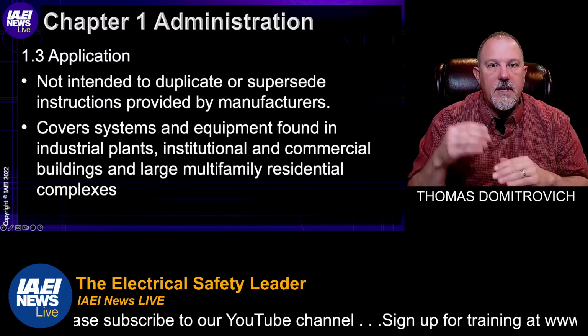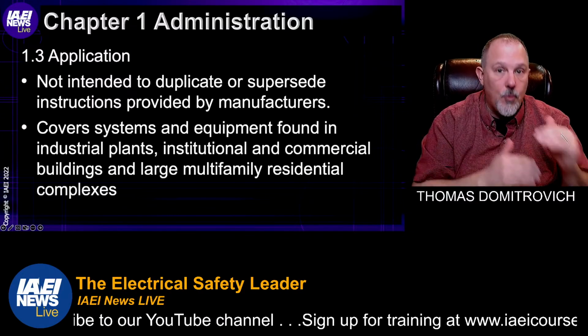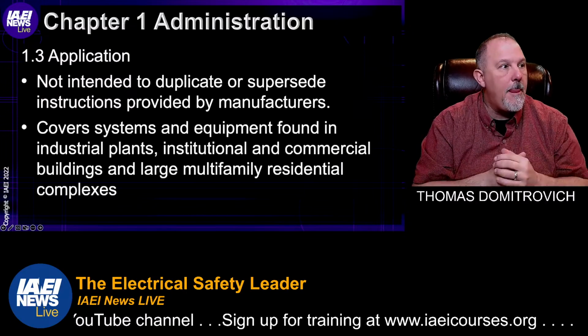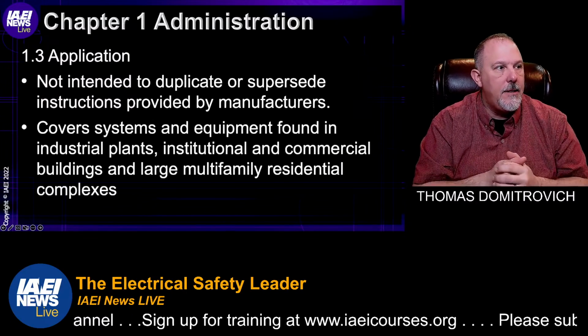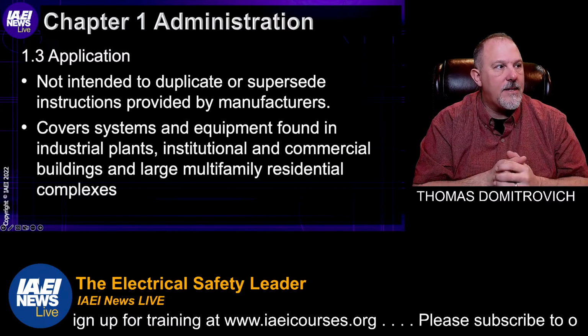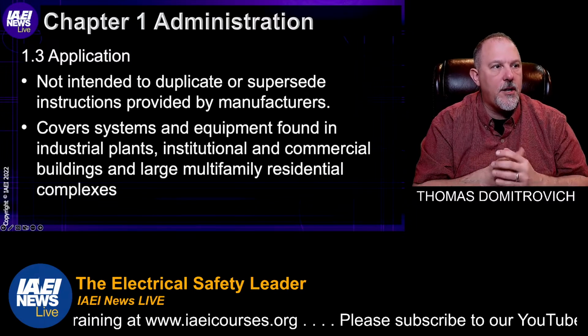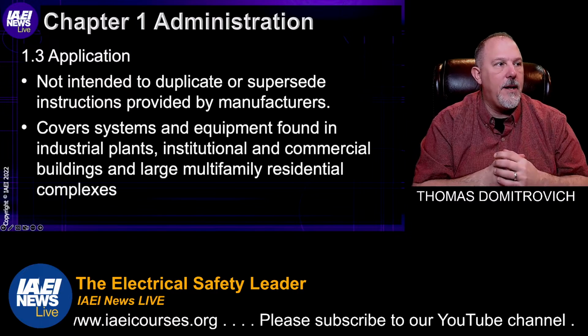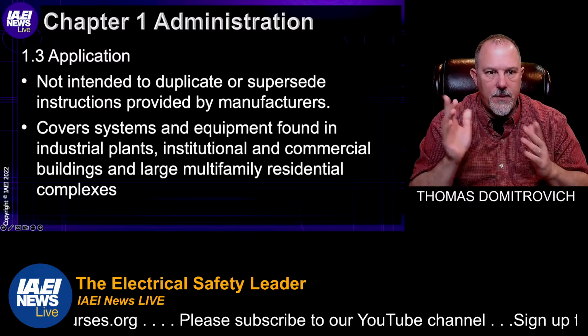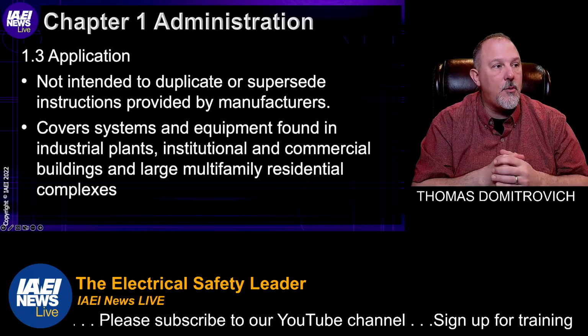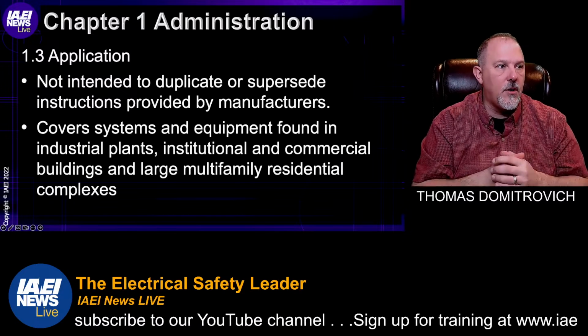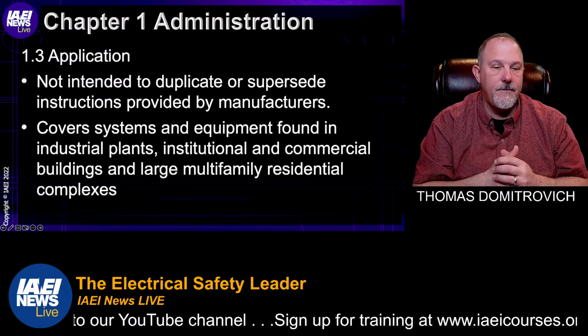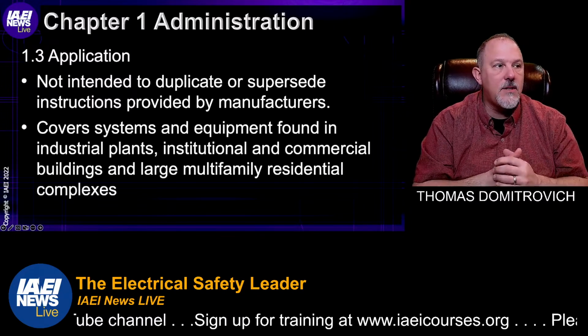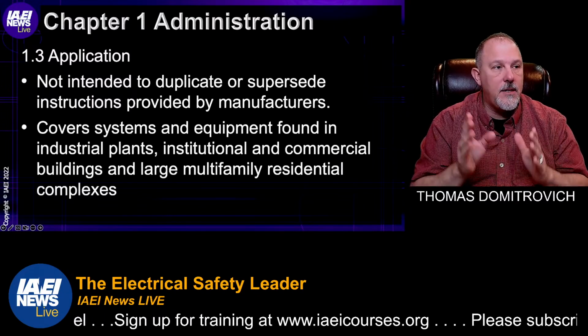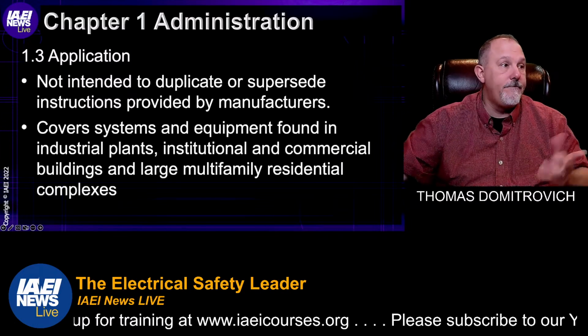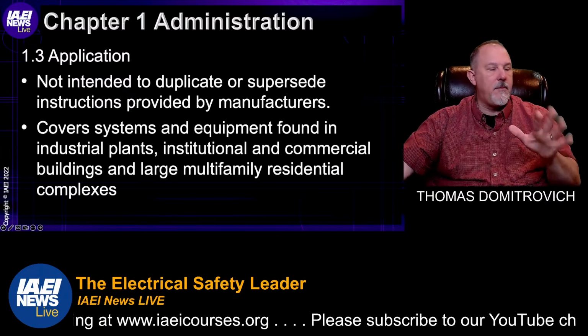Now, the question would be, does 70B apply to a residential dwelling unit? That's a different discussion. But the application section of the standard says it applies to maintenance for electrical, electronic, and communication systems and equipment and is not intended to duplicate manufacturer's instructions. Then it says systems and equipment covered are typical of those installed for industrial plants and large... but it doesn't say that it only applies to industrial plants and institutional and commercial buildings.